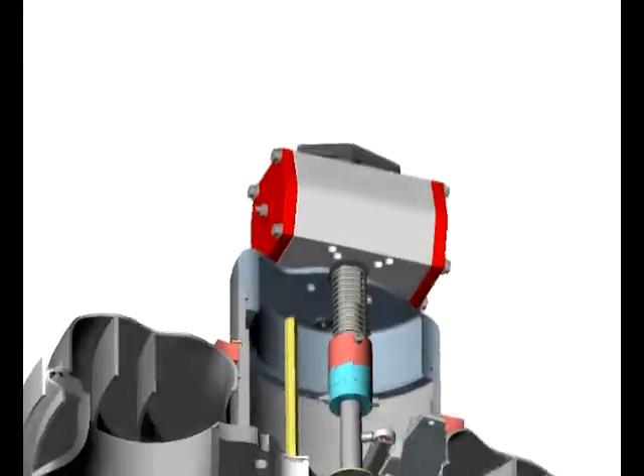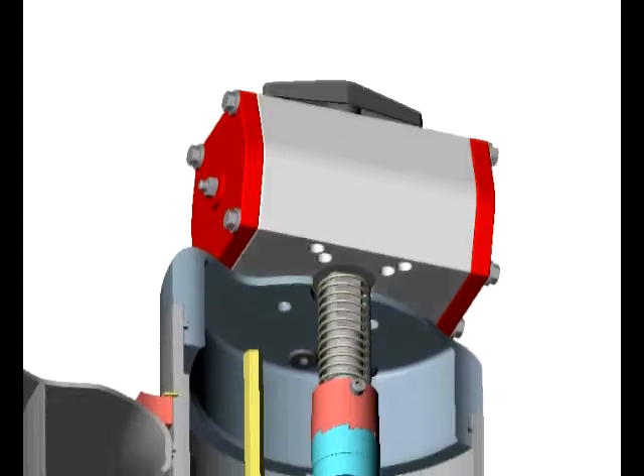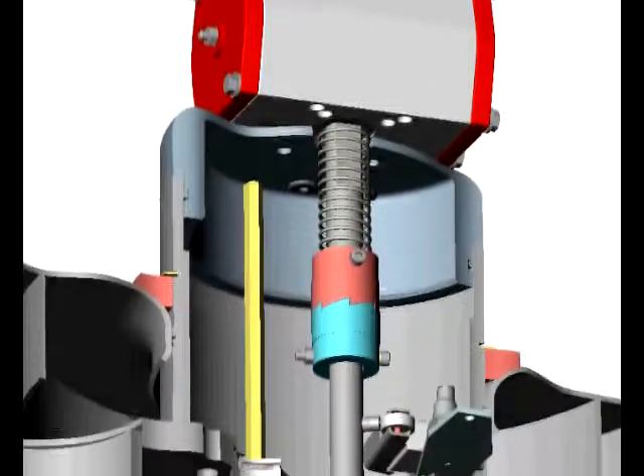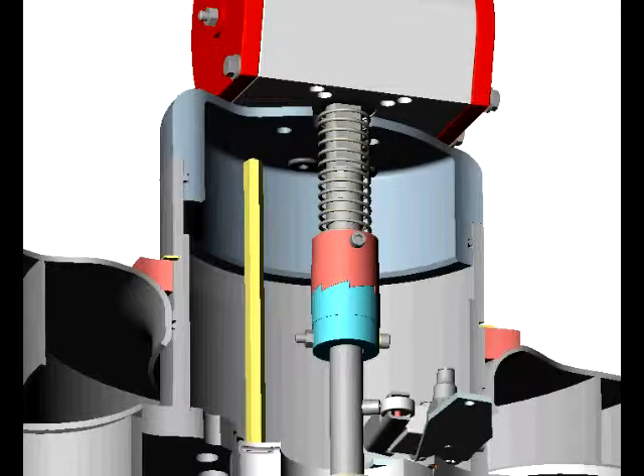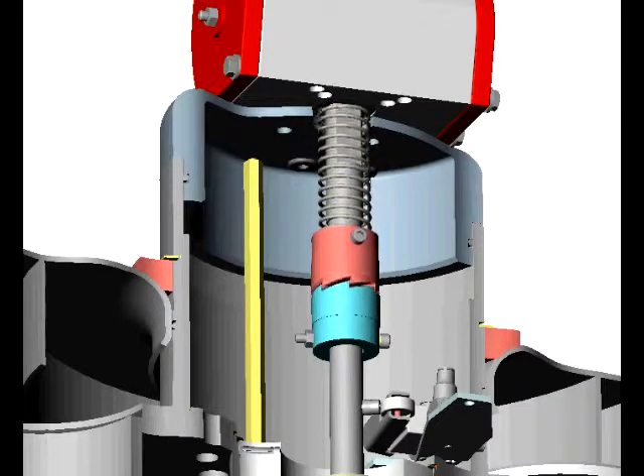We start with the upper drive shaft whose double D profile locates in the indexing actuator drive spindle. Next come the upper and lower seven tooth dog clutches. The spring maintains a contact force between the two dog clutches while still allowing vertical movement of the upper drive shaft.